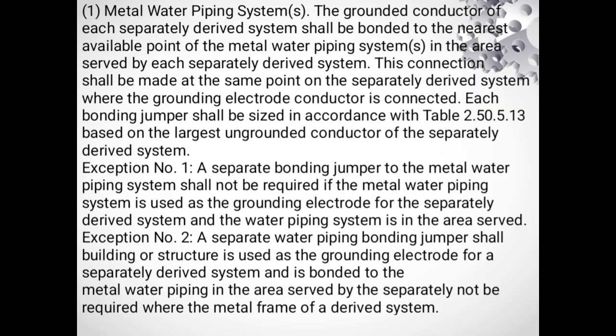Exception number 1. A separate bonding jumper to the metal water piping system shall not be required if the metal water piping system is used as the grounding electrode for the separately derived system and the water piping system is in the area served. Exception number 2. A separate water piping bonding jumper shall not be required where the metal frame of a building or structure is used as the grounding electrode for a separately derived system and is bonded to the metal water piping in the area served by the separately derived system.